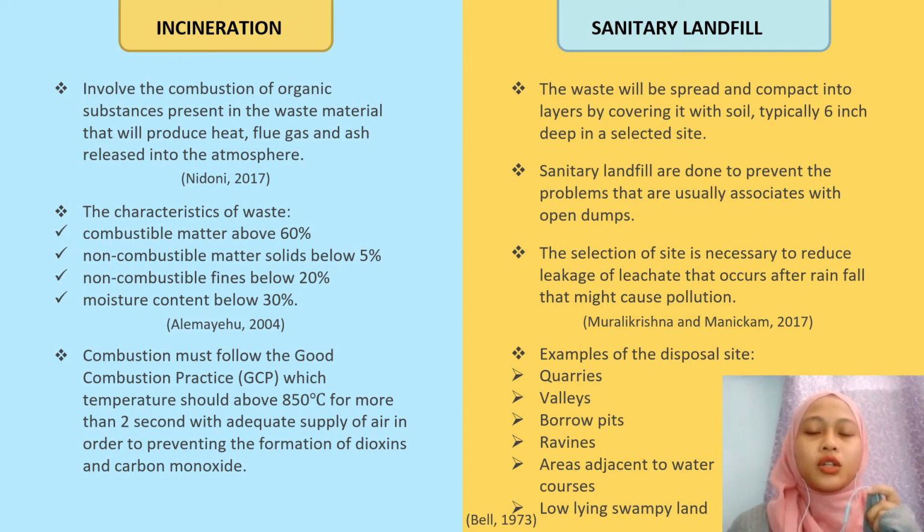The combustion process must always follow the good combustion practice, GCP, in which the temperature should be above 850 degrees Celsius for more than 2 seconds with adequate air supply in order to prevent the formation of dioxin and carbon monoxide.